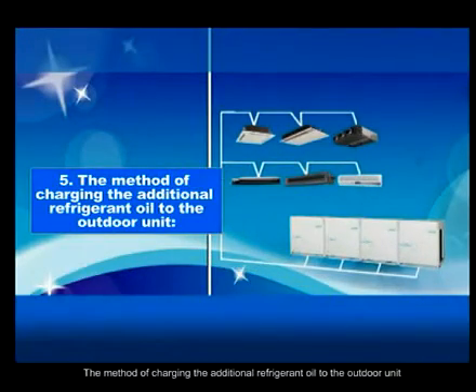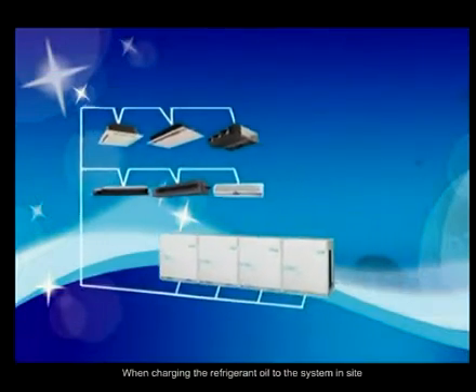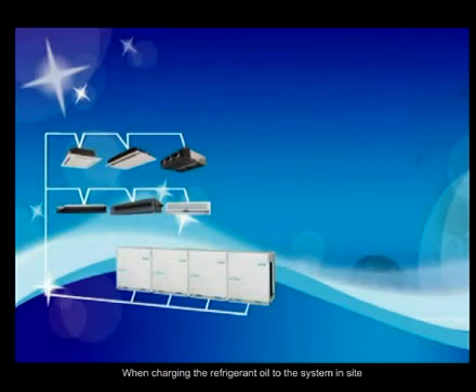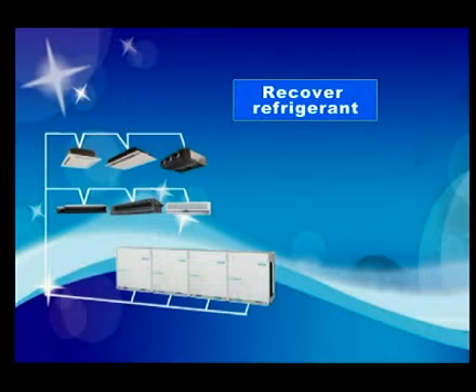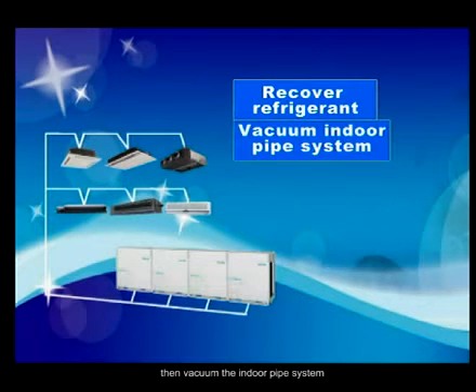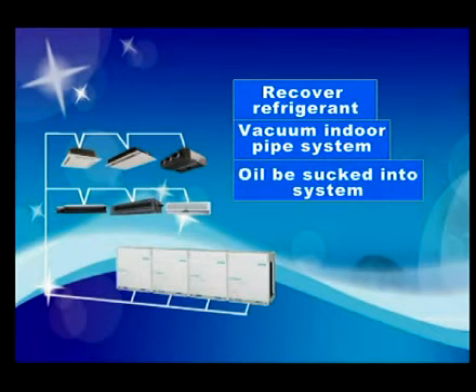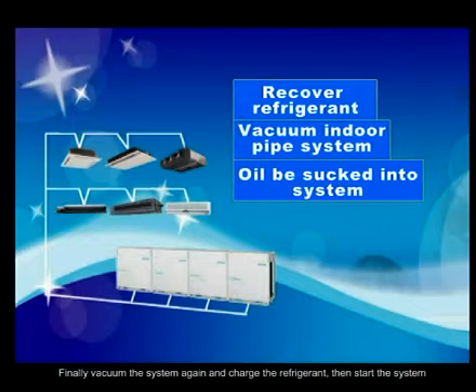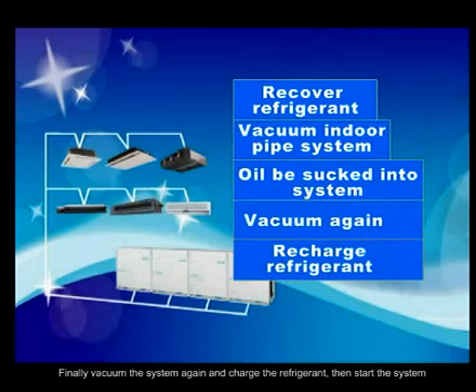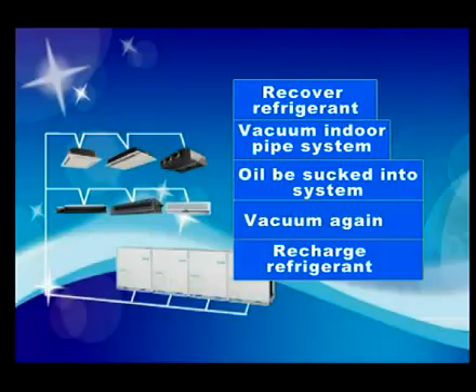The method of charging additional refrigerant oil to the outdoor unit. When charging refrigerant oil to the system, the normal procedure is to first recycle the system refrigerant to the outdoor unit, then vacuum the indoor pipe system and use the vacuum degree to suck the oil into the system. Finally, vacuum the system again, charge the refrigerant, then start the system.